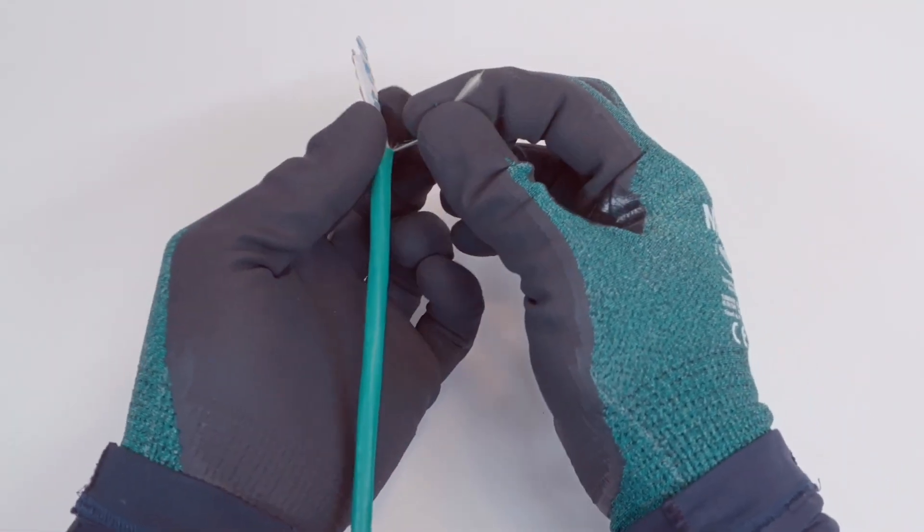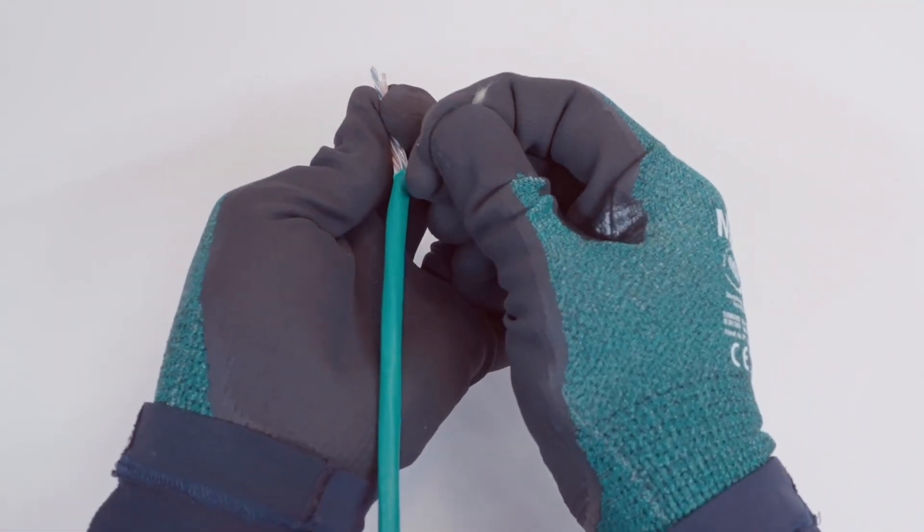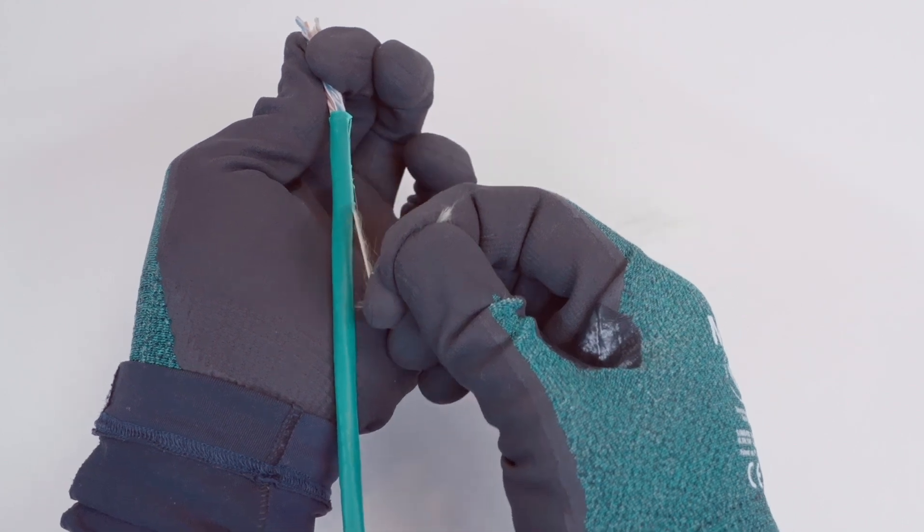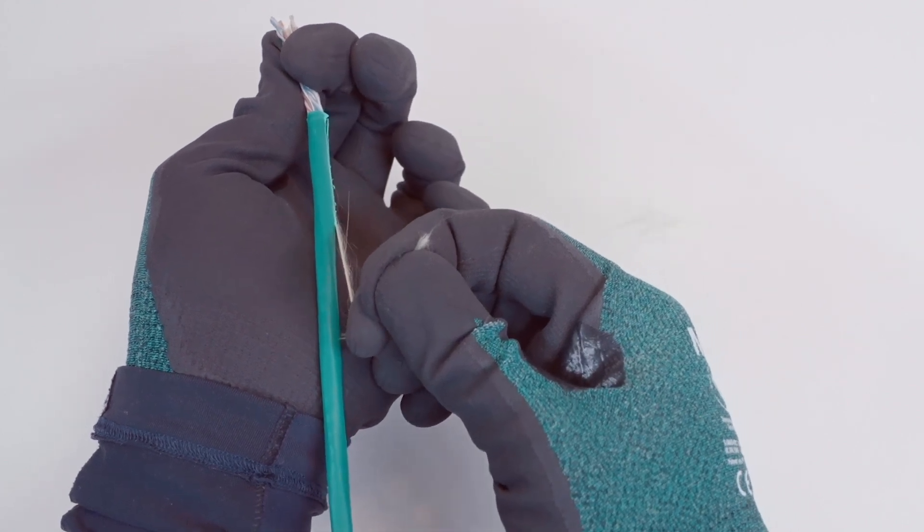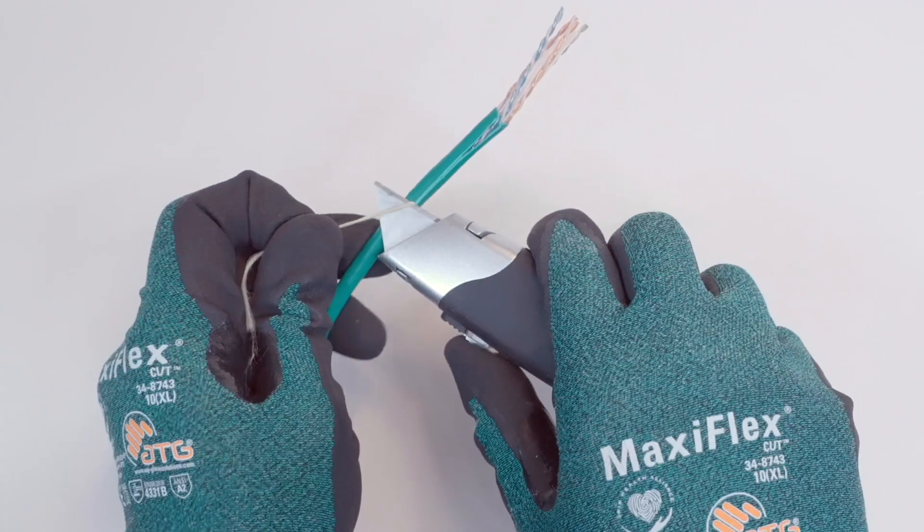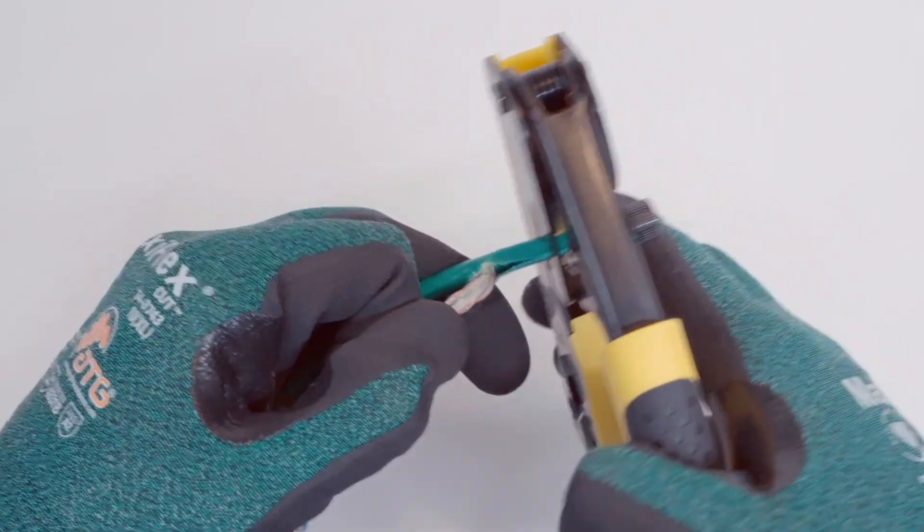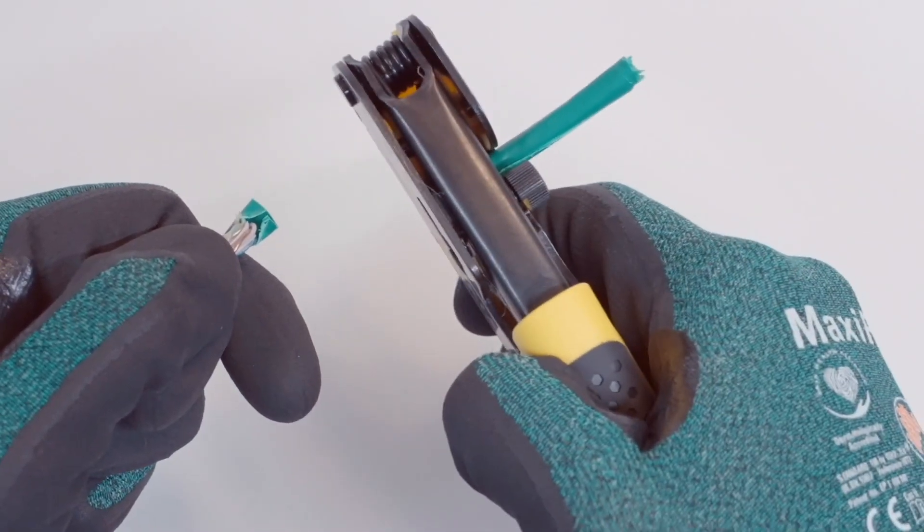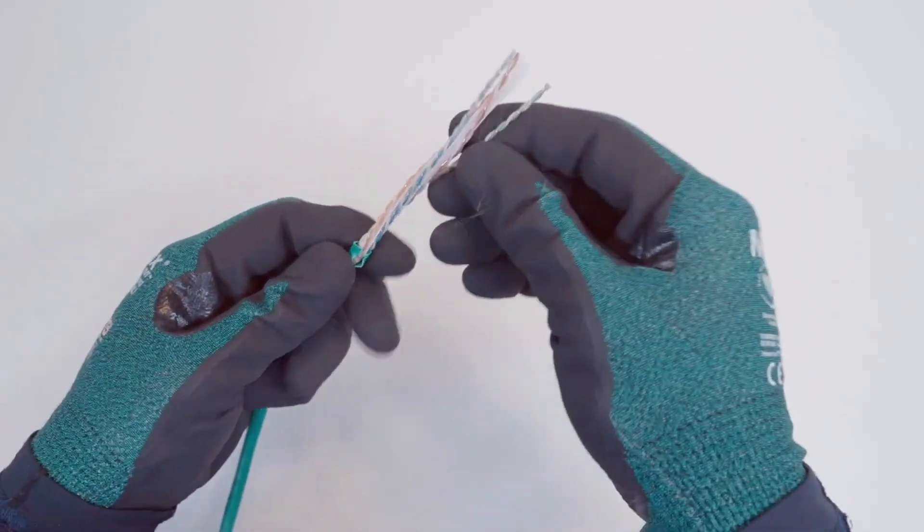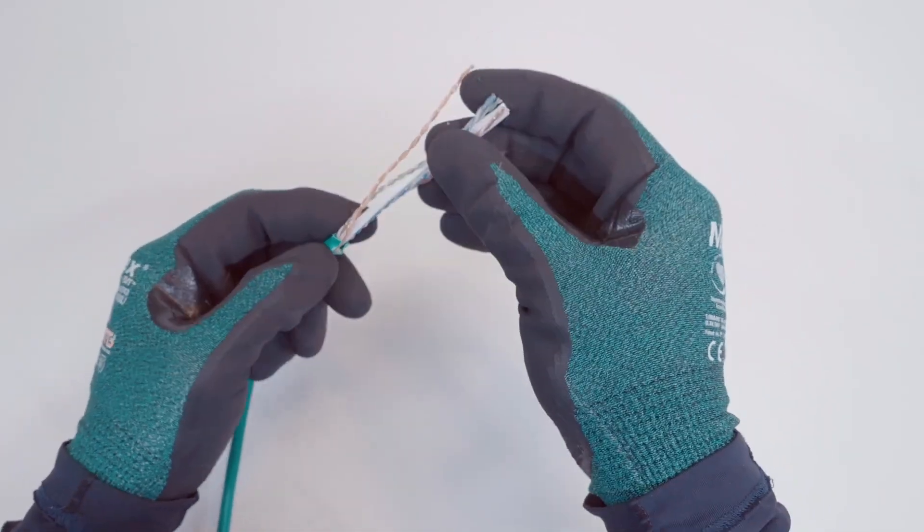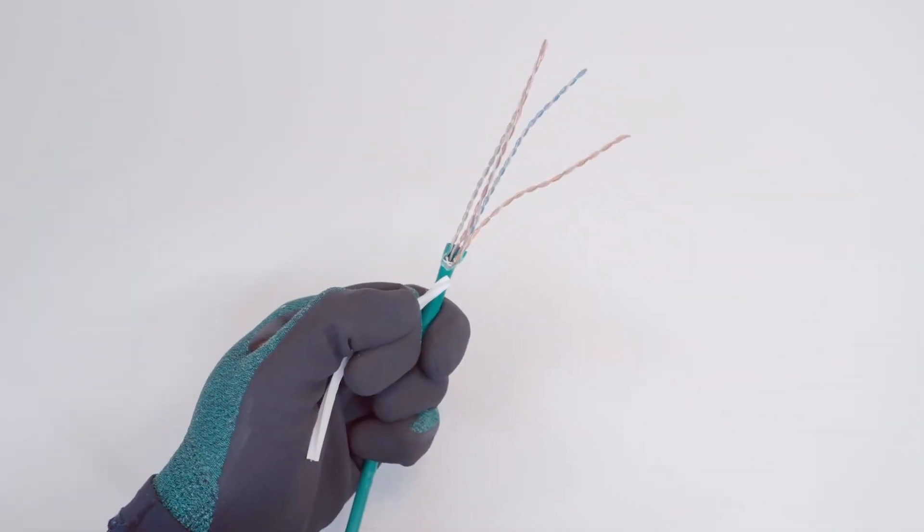Some cables include a ripcord. If present, use it as it will ensure access to a section free of damage. Pull the ripcord about a finger's worth in length. Cut off the ripcord. Bend the wires away from the jacket and carefully cut the jacket. If a separator called a spline is present, return the wires to their original position and carefully cut the spline.